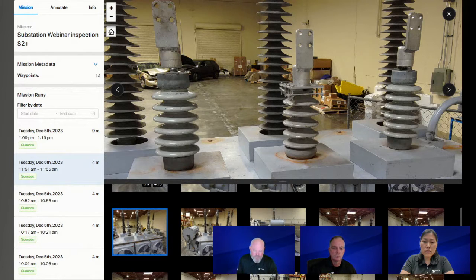But in an abnormal loading situation where you're pushing the limits on transformers, lines, buses and equipment, you can fly that switch pre-operation just with the click of a mouse. You'd be able to see if that switch is in proper adjustment and there are no thermal deficiencies. Then once you operate that switch, you give it a second and fly it again to verify it closed properly and is carrying load like it should.